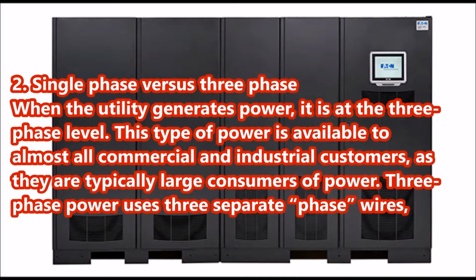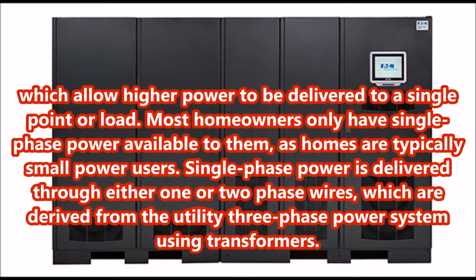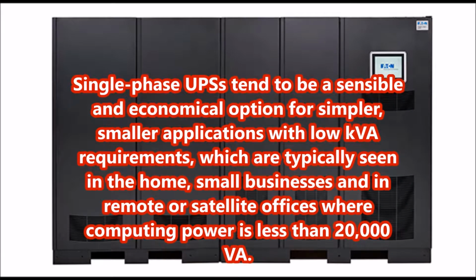Single-phase versus three-phase. When the utility generates power, it is at the three-phase level. This type of power is available to almost all commercial and industrial customers, as they are typically large consumers of power. Three-phase power uses 3 separate phase wires, which allow higher power to be delivered to a single point or load. Most homeowners only have single-phase power available to them, as homes are typically small power users. Single-phase power is delivered through either 1 or 2-phase wires, which are derived from the utility 3-phase power system using transformers.